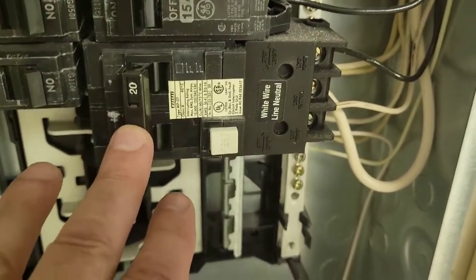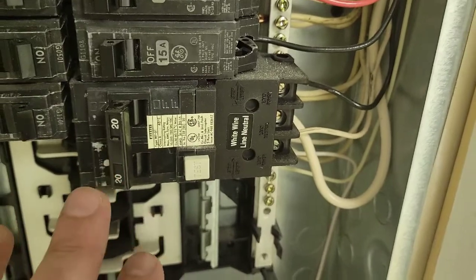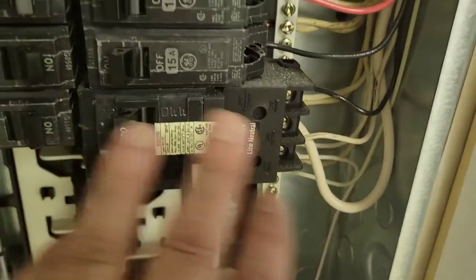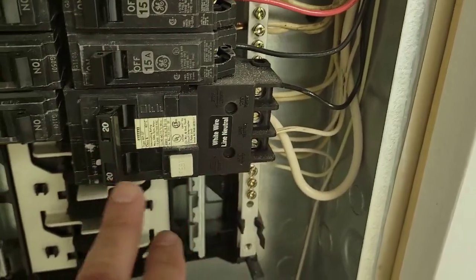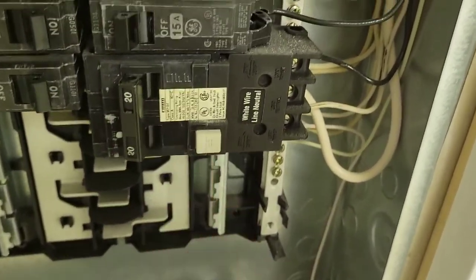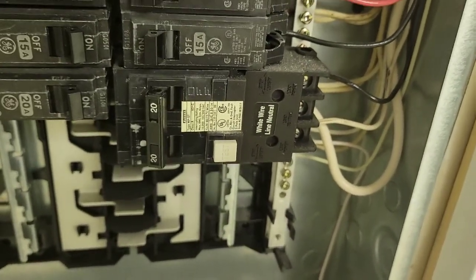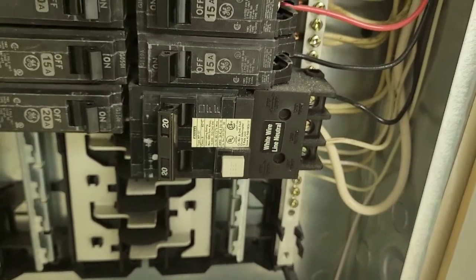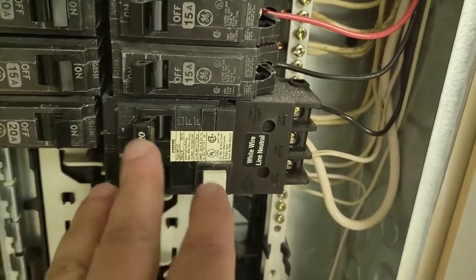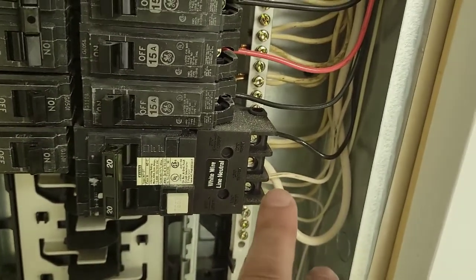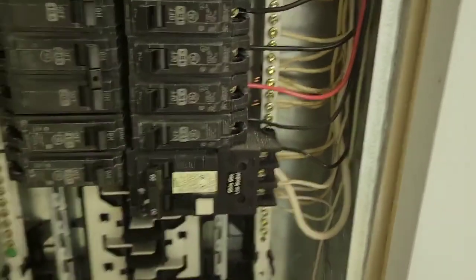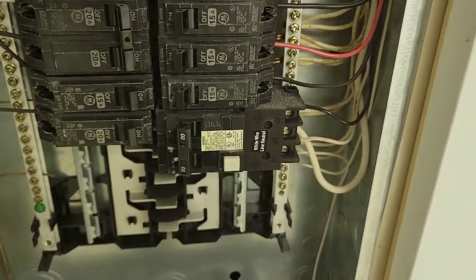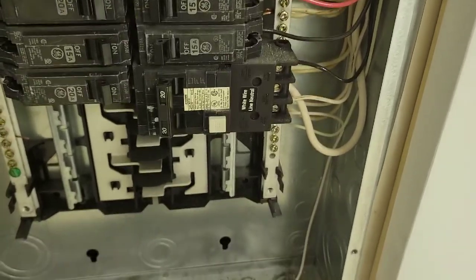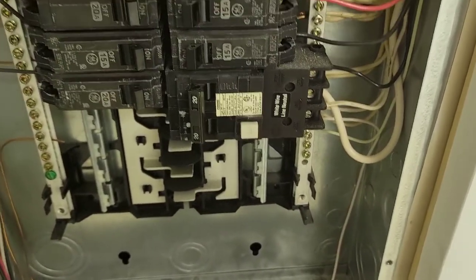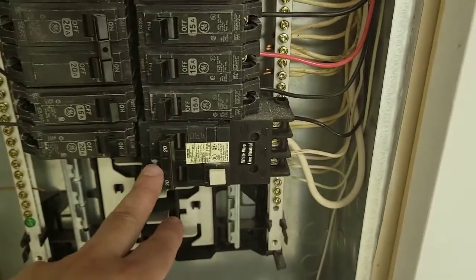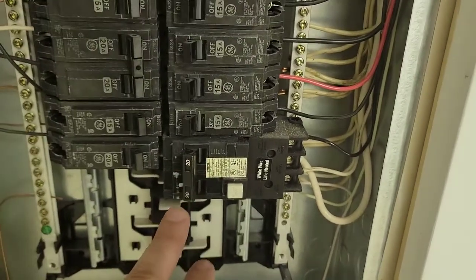I had never considered in my mind that I thought that was a 115 volt complete circuit upstairs. I never considered this because they weren't even labeled. But when we found out that this had no voltage, and the breaker had tripped, which tells me the motor probably did fail, we reset the breaker, checked the voltage, and then went back to the switch upstairs, and lo and behold, it was reading 220 or 240, whatever it was. So this breaker had tripped, and the pump and the panel are being fed by that.